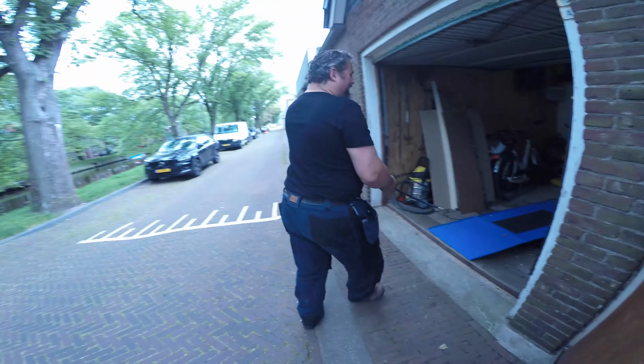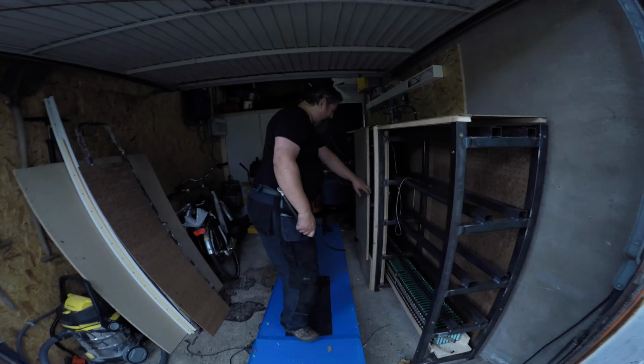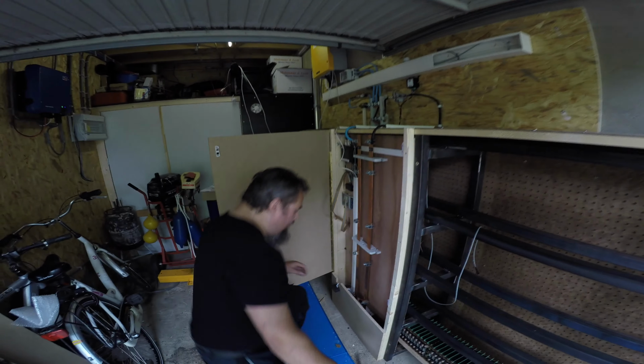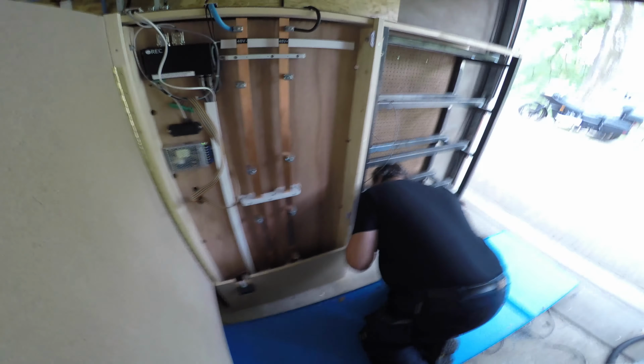We're now at the point of connecting the module to the copper strips, going from 50 square millimeter onto copper strips, 30 millimeters wide, 5 millimeters thick - so it's 150, solid copper.